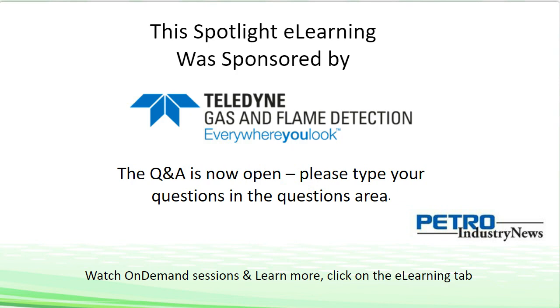Another question on hydrogen. What is the best technology for hydrogen gas detection? Is there a favored technology here? I'm going to leave that one to François. François, please. Yes, Steve. So to detect hydrogen, the easiest way is to use cat bead detectors, which is really easy when you have a standard environment, when you have O2 at 20.9% volume, and you will be able to detect any hydrogen leak. And depending on the environment, if you are indoor or outdoor, cat bead will be fine, and that's the most popular technology, I would say.